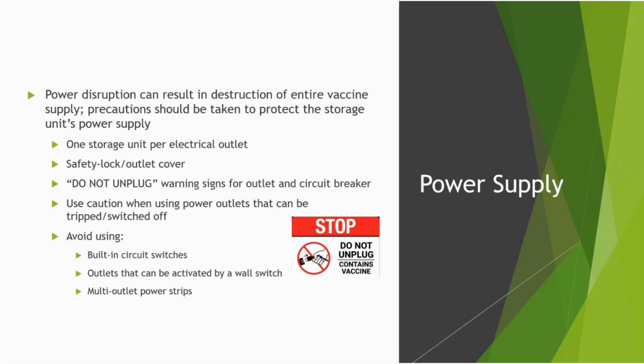They should use a safety lock plug or an outlet cover to prevent the unit from being unplugged accidentally. They should post do not unplug signs on the outlet as well as on the circuit breaker. Providers should use caution when using power outlets that can be tripped or switched off, and should avoid using built-in circuit switches, outlets that can be activated by a wall switch, and any kind of multi-outlet power strips. Next slide, please.